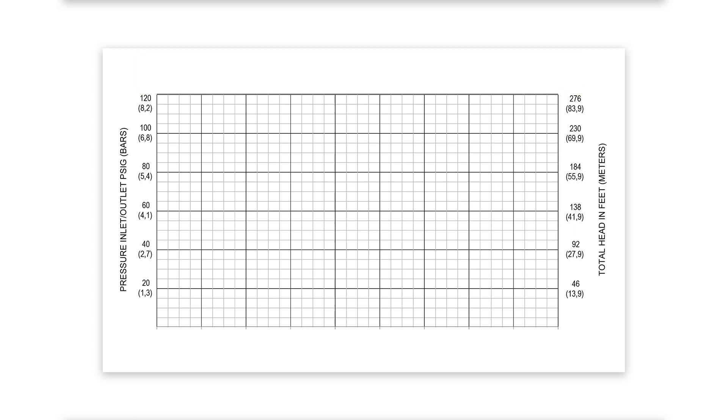Along the vertical axis is the pressure. In an AODD pump, pressure can correspond to two things: the air inlet outlet pressure in PSI and bar identified on the left-hand side, or the total head in feet and meters of water identified on the right-hand side.